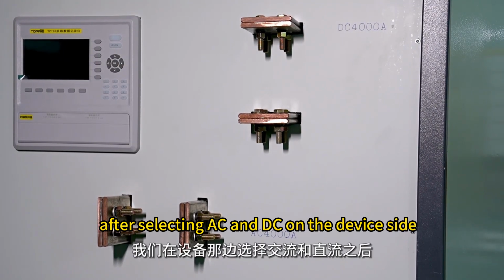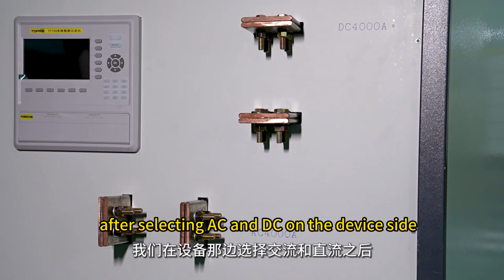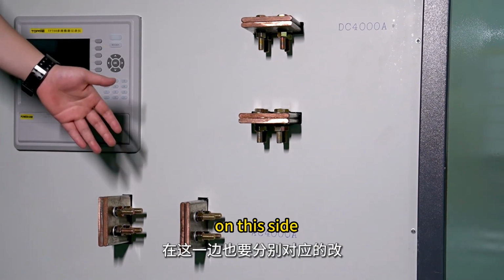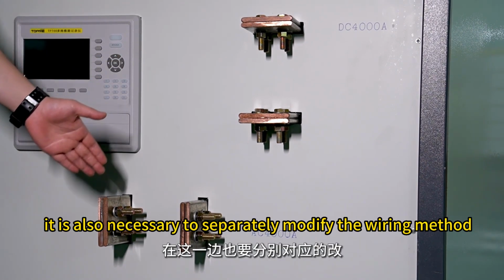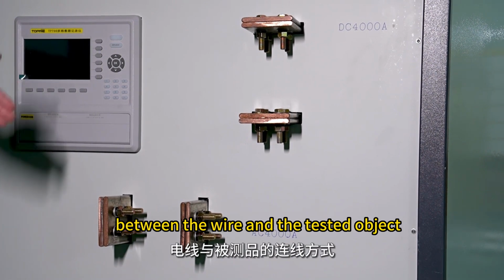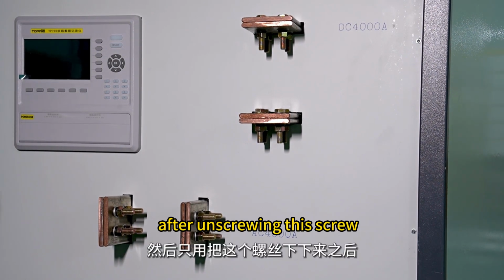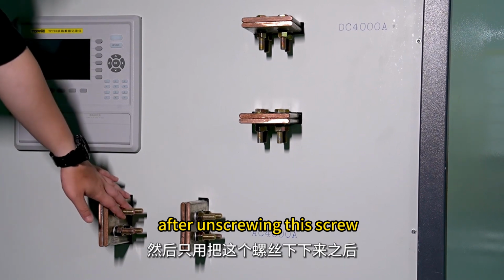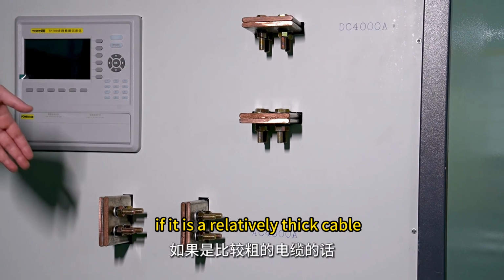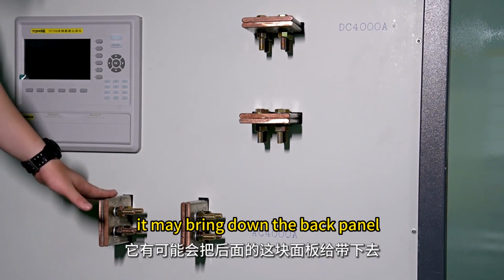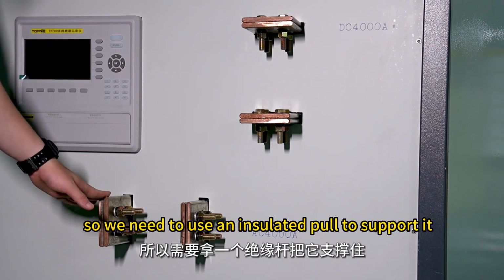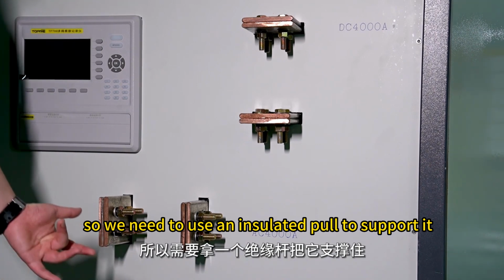After selecting AC and DC on the device side, on this side, it is also necessary to separately modify the wiring method between the wire and the tested object. After unscrewing this screw, just connect 2 cables to it. If it is a relatively thick cable, it may bring down the back panel, so we need to use an insulated pole to support it.